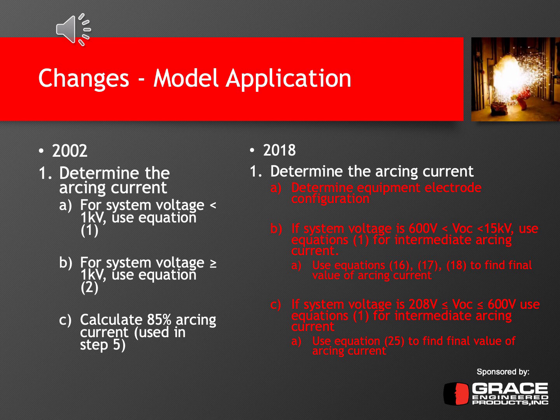And then step C, if the system voltage is between 208 volts and 600 volts, you still need to use equation 1 for the intermediate arcing current, but instead of using equations 16, 17, 18 for the final value, you use equation 25, which is a little simpler than 16, 17, 18 to find the final value of arcing current.